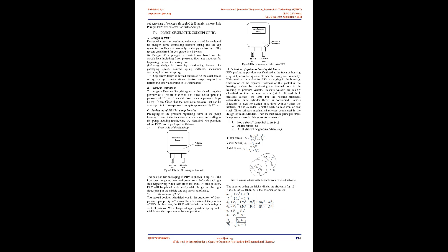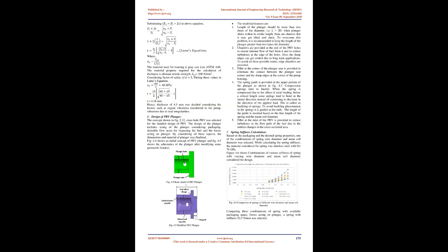This property of shape memory alloys is used for the actuation of valve. The main parts in SMA actuated PRV include SMA wires wound around a frame-like structure, a frame connected to the spool, electric supply, heat source, and a drain port, as shown in Figure 2.6. For maintaining the spool at the lowermost position, i.e. at seated position, continuous supply of electric current is given to the heat source, which in turn generates heat and transfers it to the SMA wires.